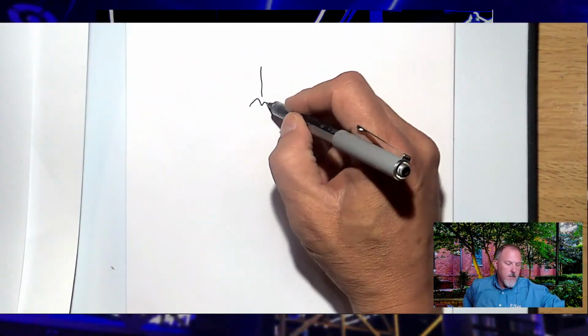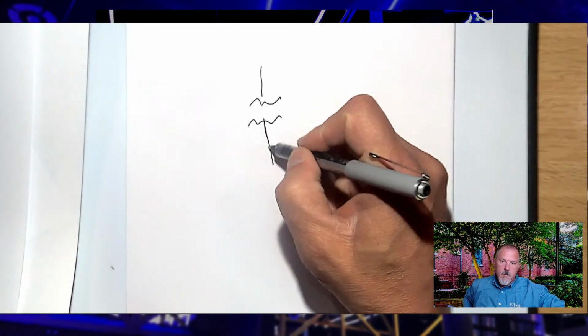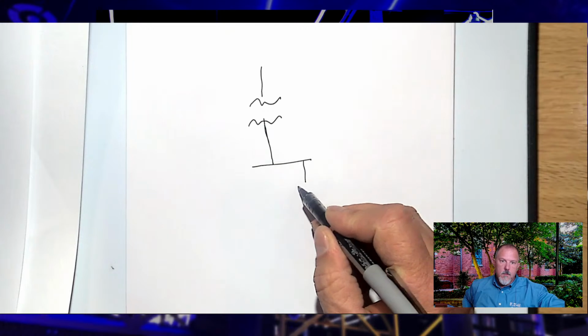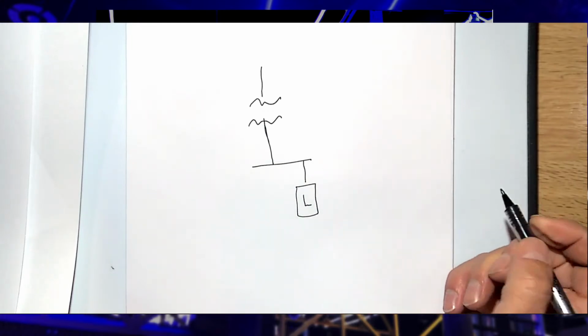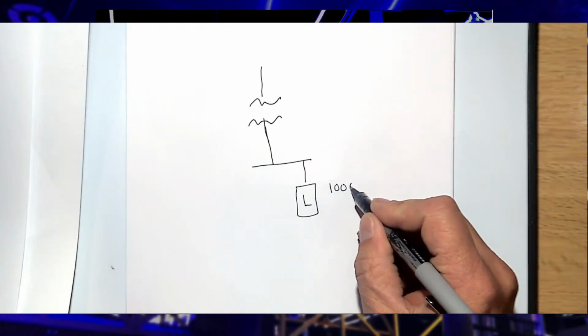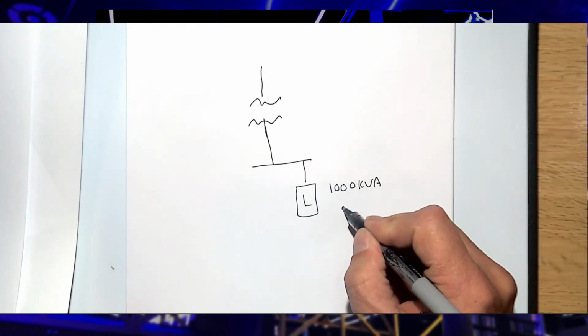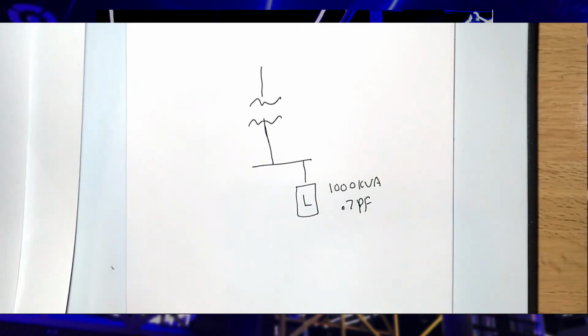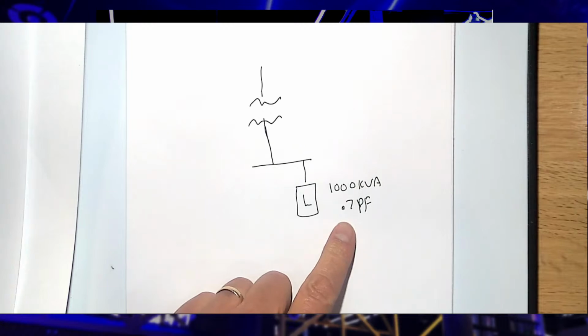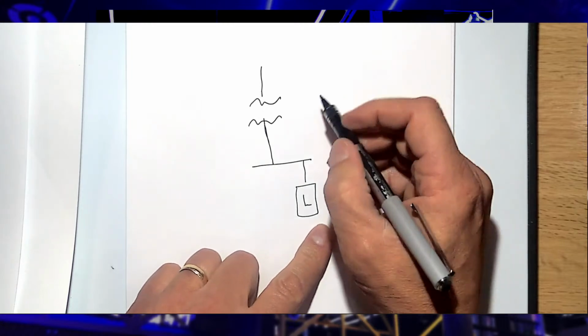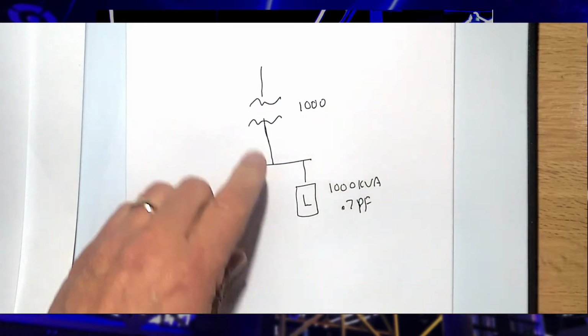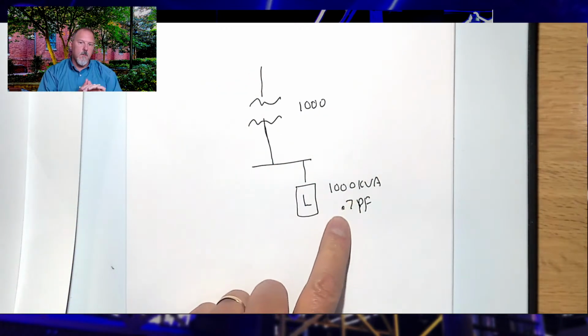So let's go back to that example. I'll make up an example here and show you one. If we look at the power system, here's our transformer, the utility company. And we have a load and we have a bunch of motors, and our load is, let's say, a poor power factor. Let's say it's 1,000 kVA at 0.7 power factor. Let's say this is a 1,000 kVA transformer. Well, I can only supply this load at 1,000 kVA at 0.7 power factor.